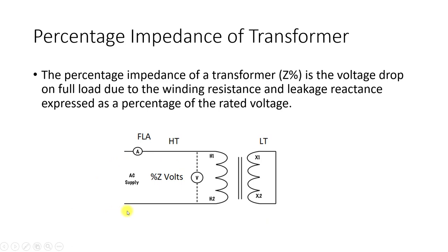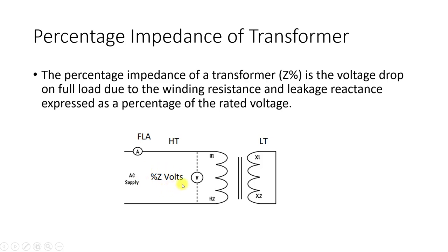Connect a variable AC source to the high-voltage side and increase the voltage very slowly and carefully while measuring the current. When the current reaches the full load amperes at the HV side, stop increasing the voltage and measure the voltage reading. This measured voltage is the impedance voltage — it represents the voltage drop that will appear from no load to full load for the transformer.